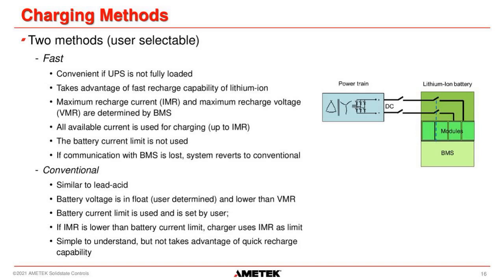If you're using the fast method, the charger will supply as much current as it has available up to the IMR value. There is no battery current limit in this case, because the battery current limit is now replaced with the IMR, which is set by the battery. And if communication between the UPS and the battery is lost, the UPS will revert to the conventional method of charging that I'm going to talk about now.